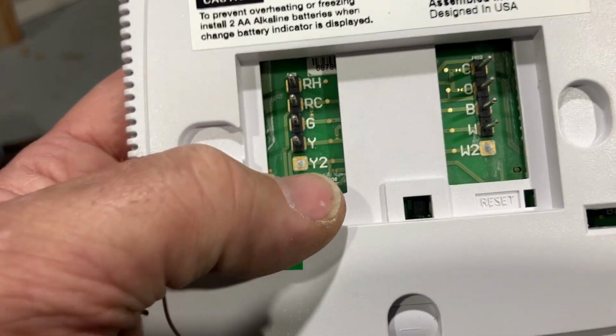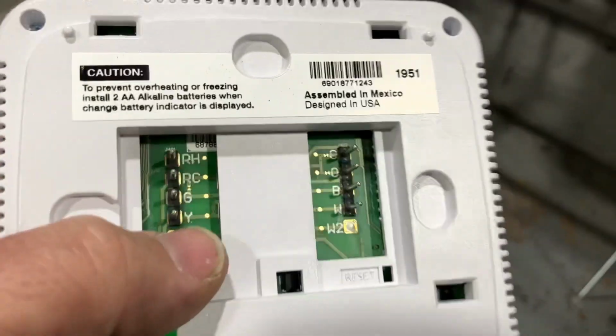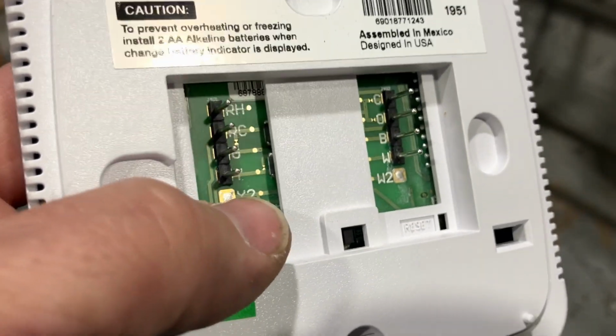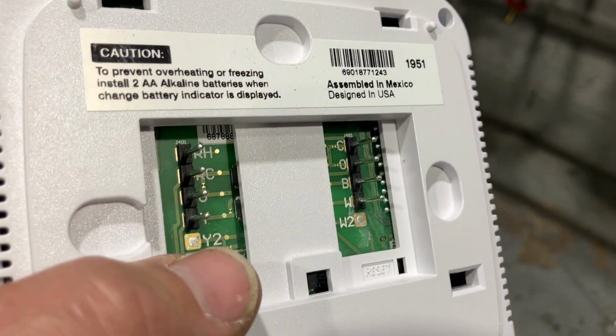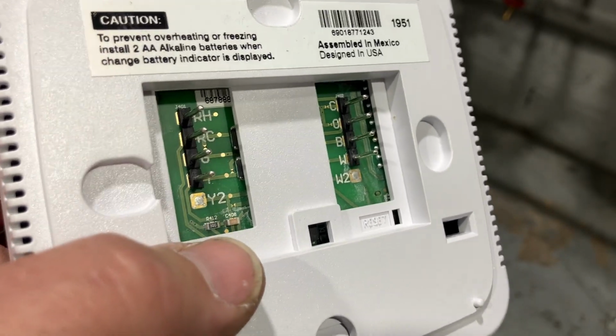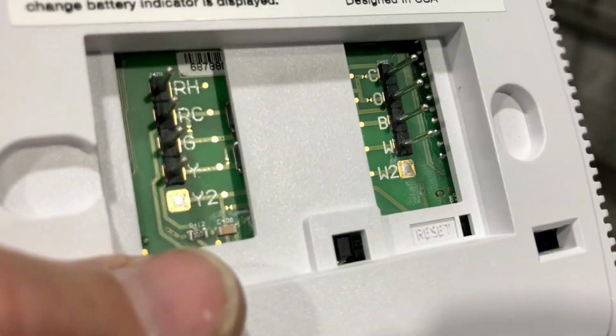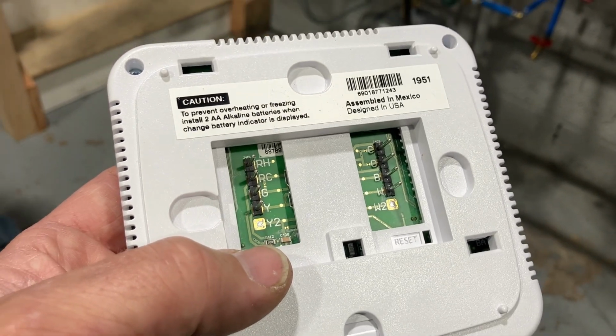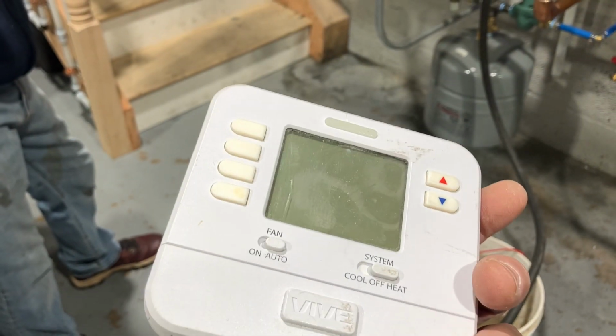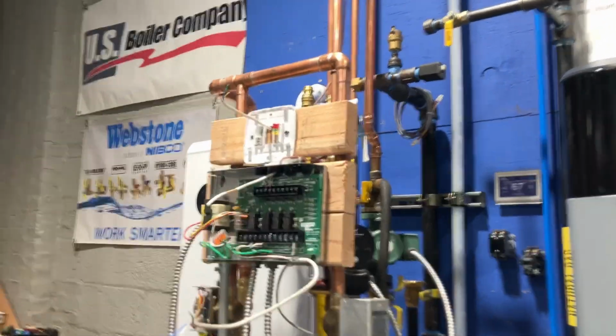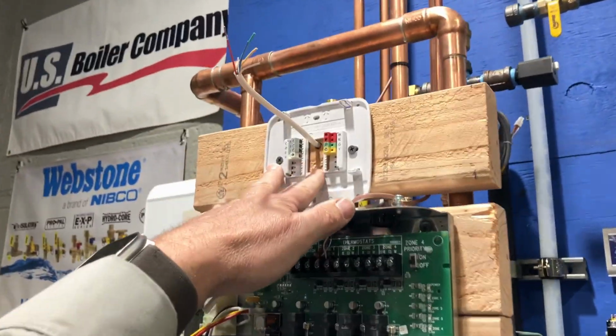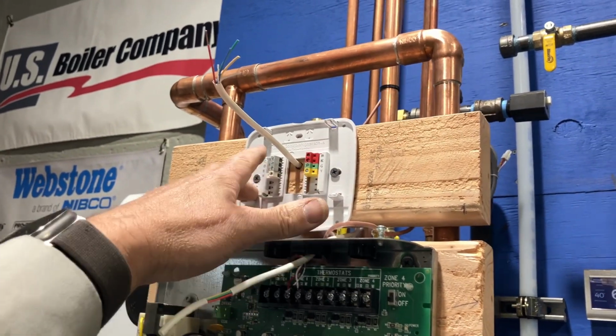There's no Y2, even though you could have that on an upgraded model, because there's no pin on the terminal. C is common, O and B is your reversing valve, W is your heating circuit. W2 is also not there; that would be an upgraded model of this. Standard thermostat, nothing crazy, right? We have the mounting bracket, or the wall bracket, on the wall. All of our terminals line up there as well.